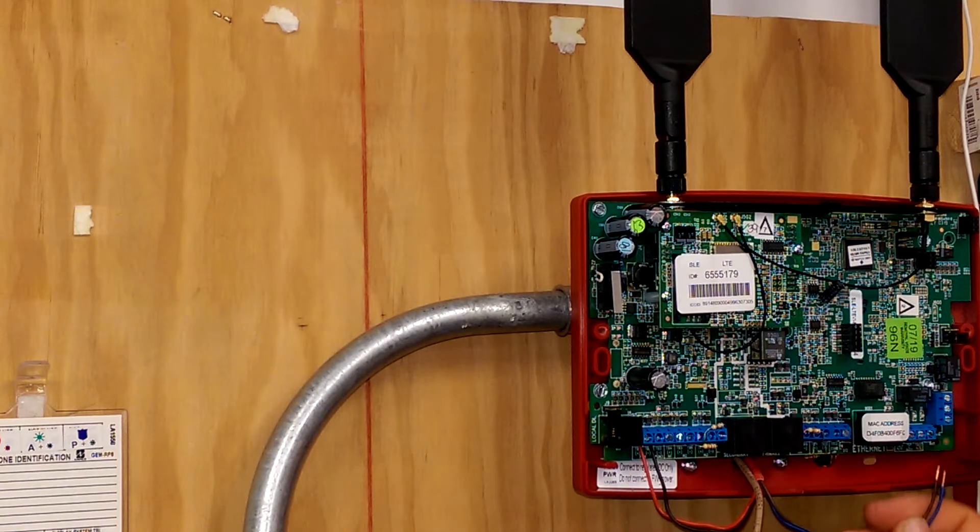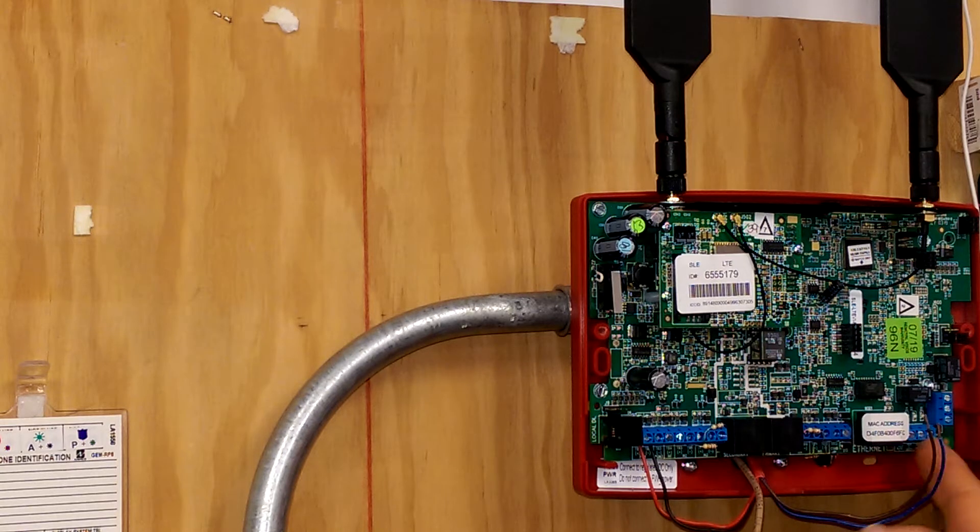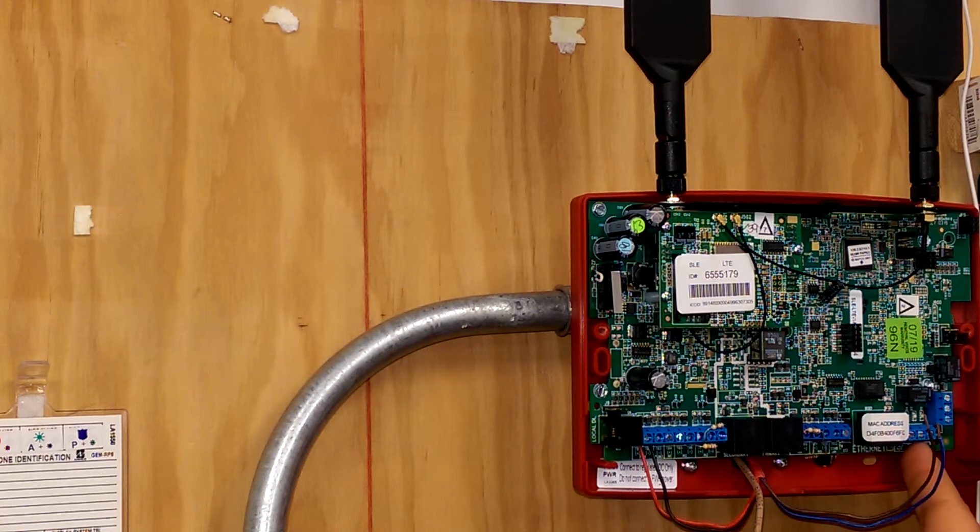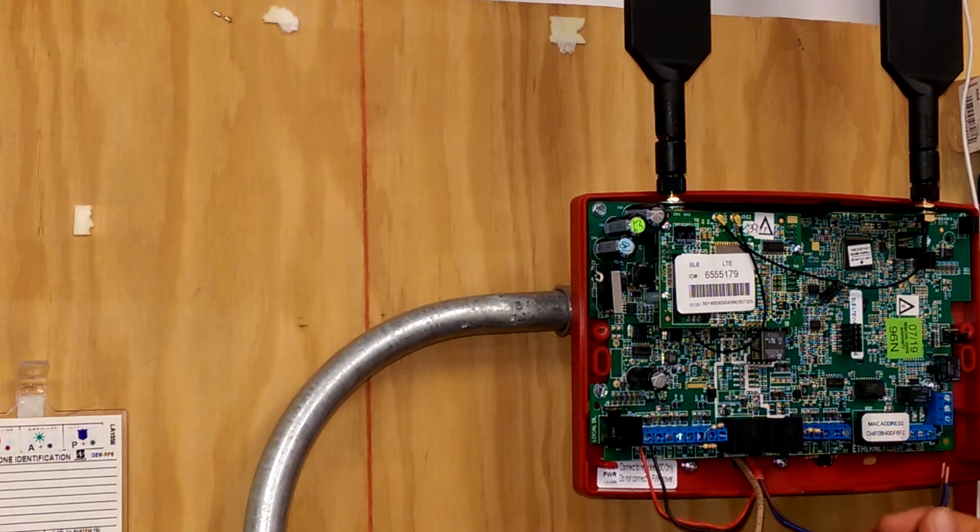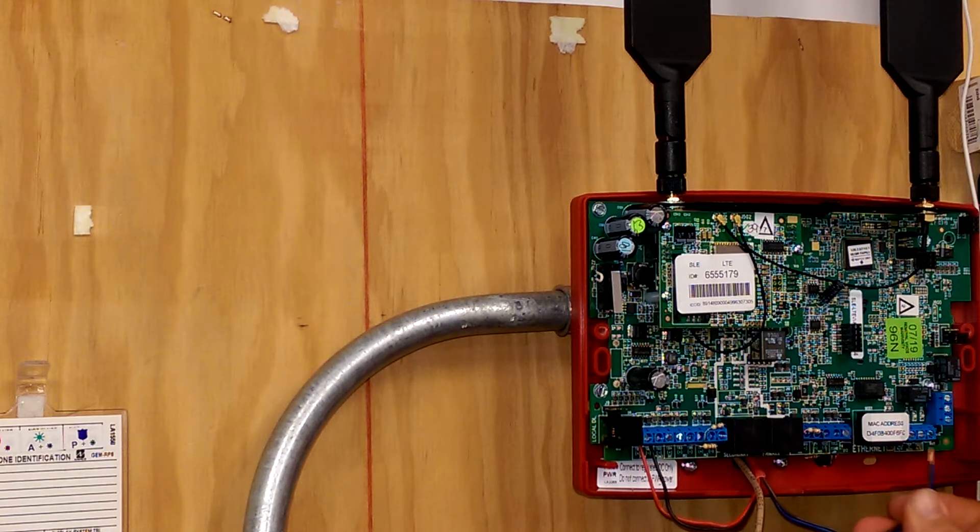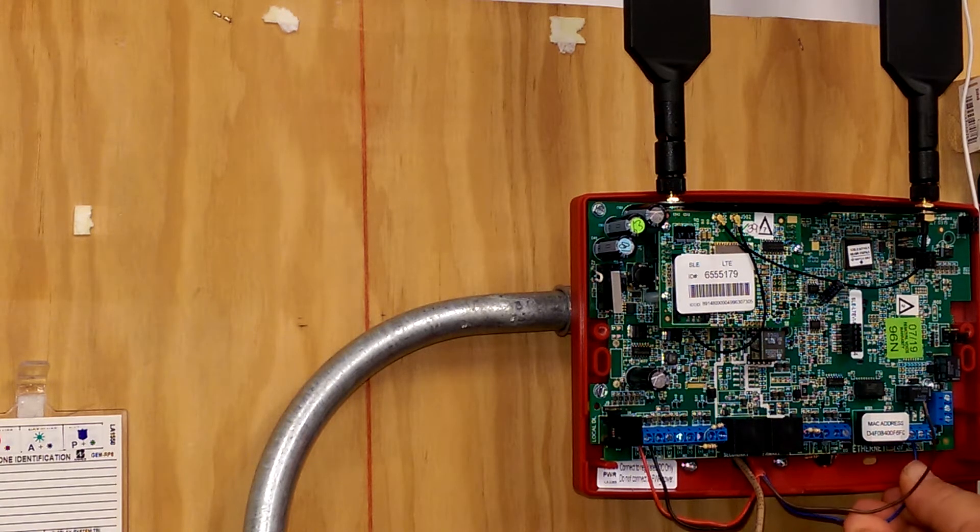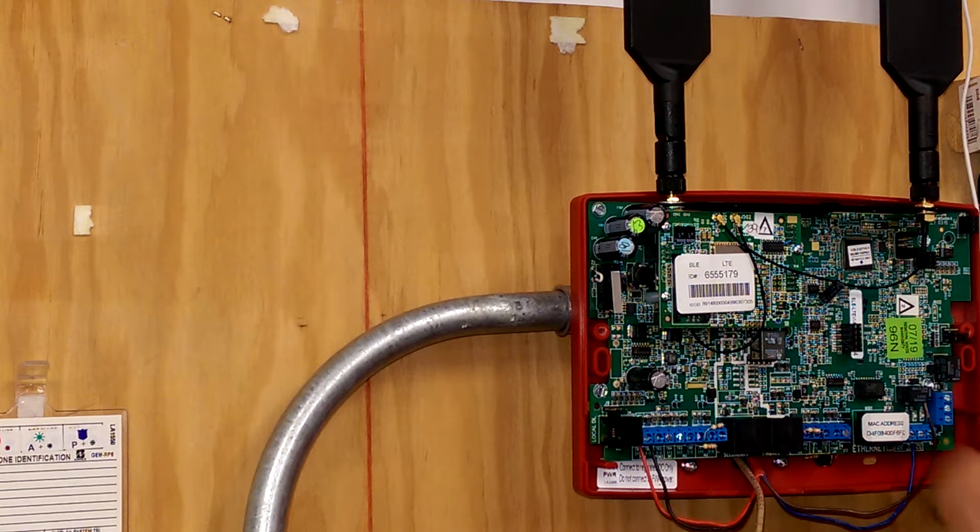Next, we're going to wire our trouble zone to output number one, the form C relay on the radio. This can be wired normally open or normally closed, whatever you need for your particular application.